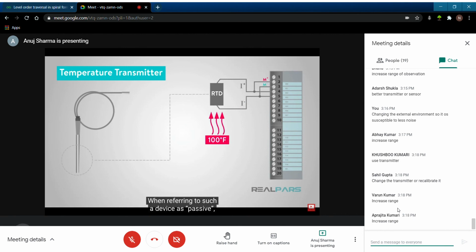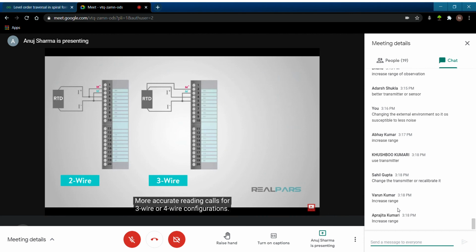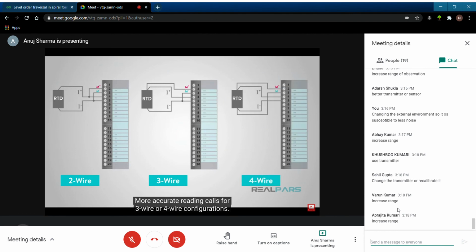When referring to such a device as passive, it means that the device needs an external current or voltage source. To state the obvious, a big amount of external current can cause power dissipation in the resistor of RTD and lead to excess heat. So to avoid this type of error, the current should be kept at a minimum level. This wiring diagram shows the simplest application of an RTD, called two-wire configuration. More accurate reading calls for three-wire or four-wire configurations.